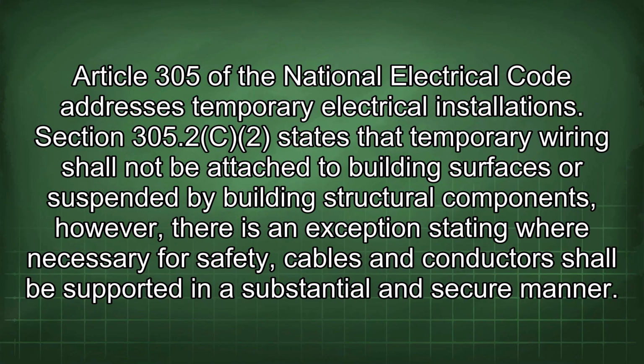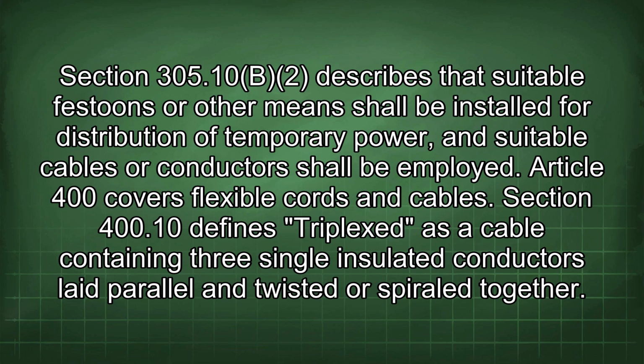Article 305 of the National Electrical Code addresses temporary electrical installations. Section 305.2c2 states that temporary wiring shall not be attached to building surfaces or suspended by building structural components. However, there is an exception stating where necessary for safety, cables and conductors shall be supported in a substantial and secure manner. Section 305.10b2 describes that suitable festoons or other means shall be installed for distribution of temporary power, and suitable cables or conductors shall be employed.